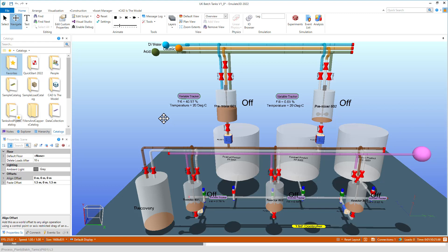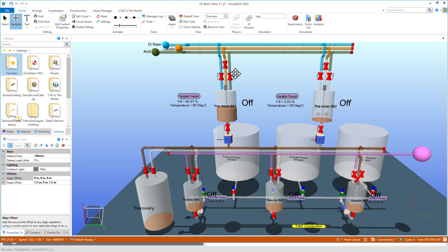For example, for each of the valves you can see on the top of the pre-mixer here, Emulate 3D is reading the solenoid control output from our process controller. When it sees that change, it will simulate the valve opening and then send back the feedback for the valve, such as the open and closed limit switches when the valve reaches those positions.